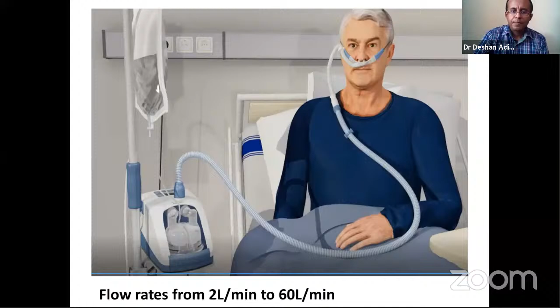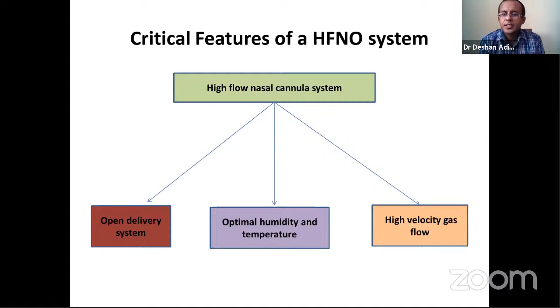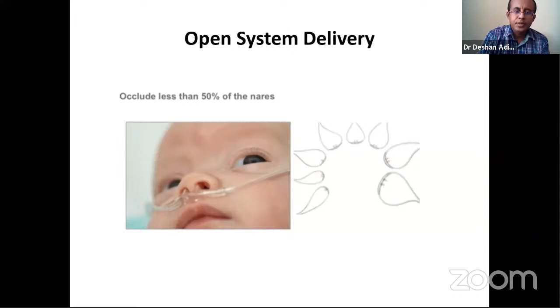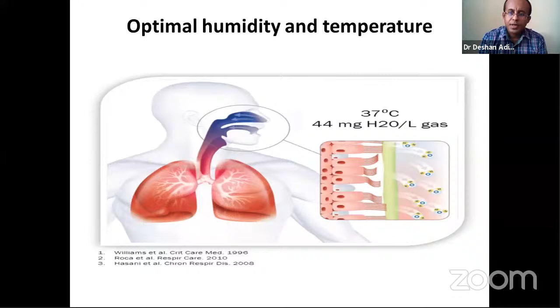Just to show you the critical features of a high flow nasal oxygen system: basically it's an open delivery system which provides optimal humidity at optimal temperature with high gas velocities. Open system means the nasal prongs only cover 50% of the nares. It's kept open for the mechanisms to work. It provides optimal humidity and temperature, 37 degrees Celsius, so that the mucosa is not dried off, which helps mucociliary function and prevents airway obstruction.